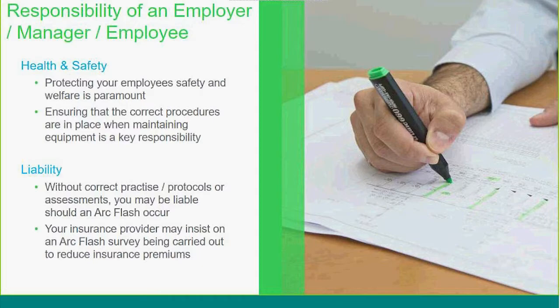However, there have been a couple of prosecutions of late in 2017 from the Health and Safety Executive around the operation and switching of electrical equipment, where they have specifically mentioned arc flash potential. So this is almost like a duty of care. It's not mandatory. However, it's probably very good engineering practice to first of all understand the magnitude of the fault current at every point on your network. And the Electricity at Work Act Regulation 5 very clearly points to that. It talks about the strength and capability of the installed equipment.